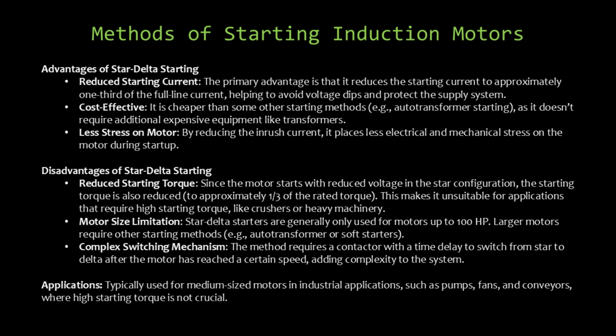Despite its benefits, star-delta starting has notable limitations. The reduced voltage in the star configuration means reduced starting torque, typically only 1/3 of the rated torque. This makes it unsuitable for applications requiring high starting torque, such as crushers or heavy machinery. Generally, these starters are limited to motors up to 100 HP, with larger motors requiring alternative starting methods.